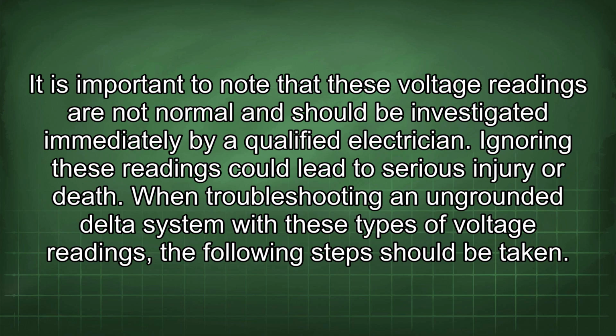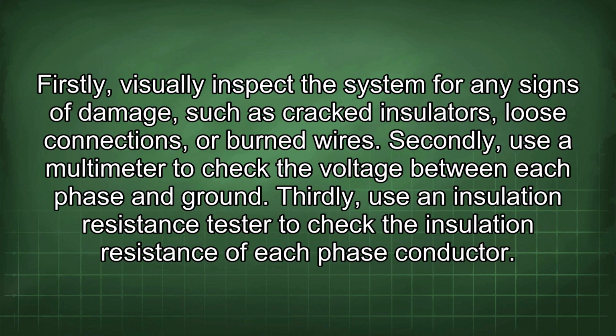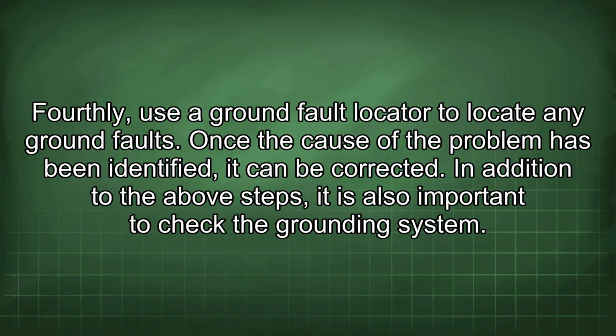When troubleshooting an ungrounded delta system with these types of voltage readings, the following steps should be taken. Firstly, visually inspect the system for any signs of damage, such as cracked insulators, loose connections, or burned wires. Secondly, use a multimeter to check the voltage between each phase and ground. Thirdly, use an insulation resistance tester to check the insulation resistance of each phase conductor. Fourthly, use a ground fault locator to locate any ground faults. Once the cause of the problem has been identified, it can be corrected.